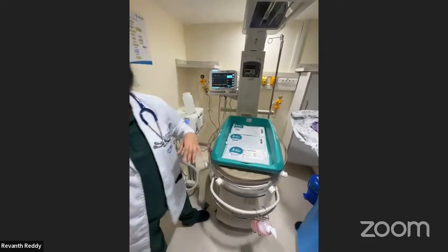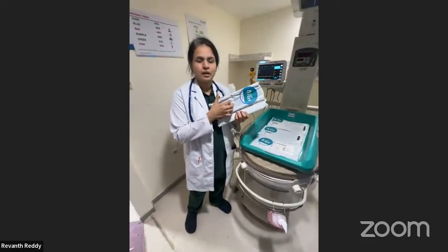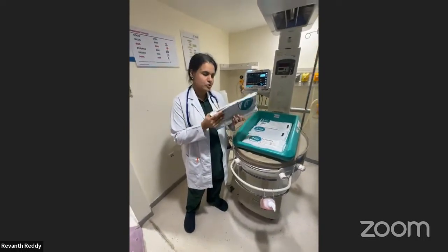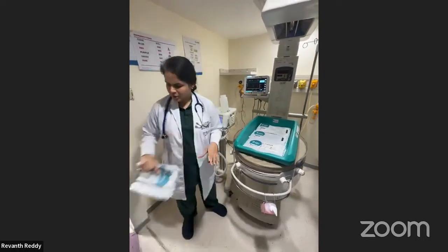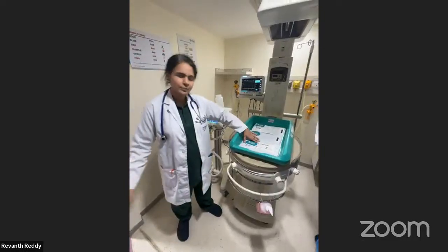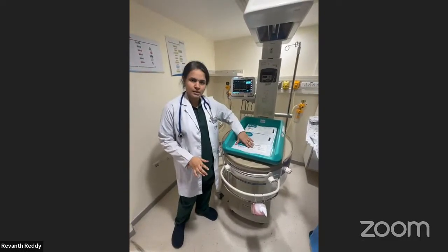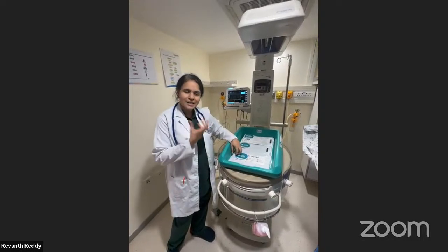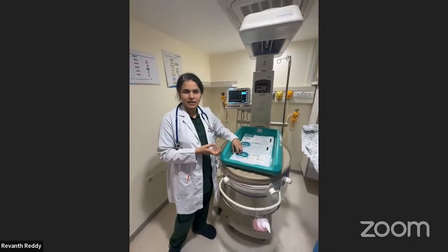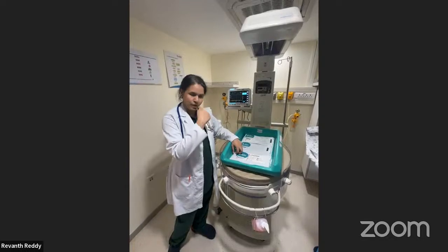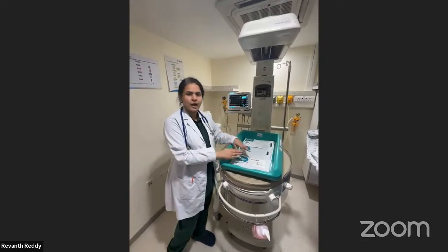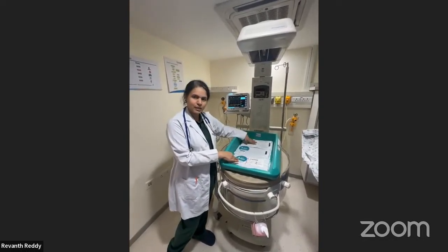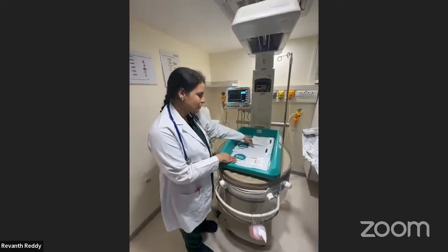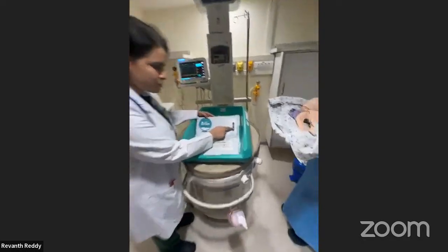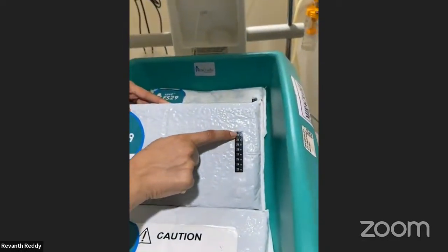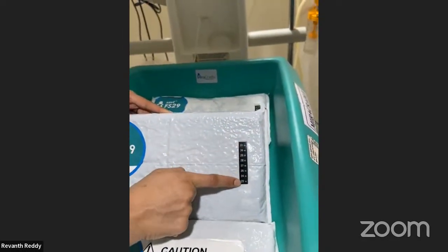The manufacturer generally provides some additional FS29 mattresses, which you can keep as backup, because during one session of 72 hours cooling, very likely by 24 to 36 hours, this may become heated up because it keeps absorbing the baby's heat and might change into the liquid phase. Then you will have to keep it back in the refrigerator and take the other set of FS29 mattresses. Even while the cooling phase is going on, you will be able to see the temperature that is being displayed here against the FS29 mattress.